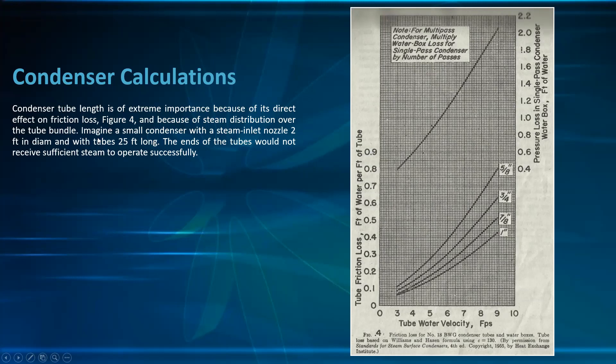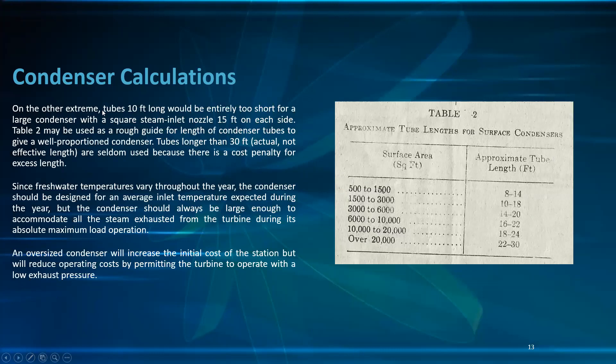Imagine a small condenser with a steam inlet nozzle 2 feet in diameter with tubes 25 feet long — the ends of the tubes would not receive sufficient steam to operate successfully. Conversely, tubes 10 feet long would be entirely too short for a large condenser with a square steam inlet nozzle 15 feet on its side. Table 2 may be used as a rough guide for length of condenser. Tubes longer than 20 feet effective length are seldom used because of cost penalties.